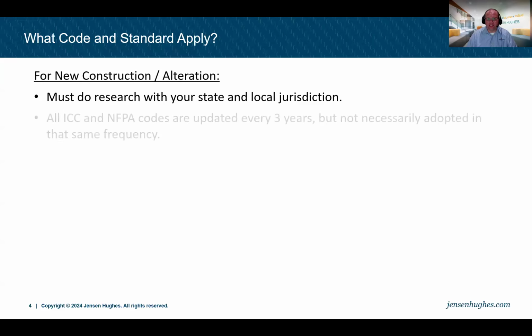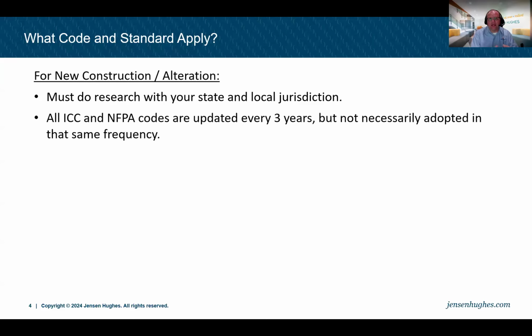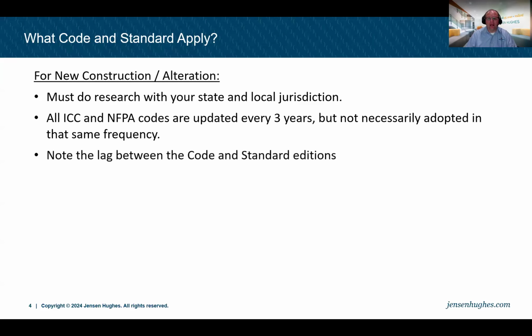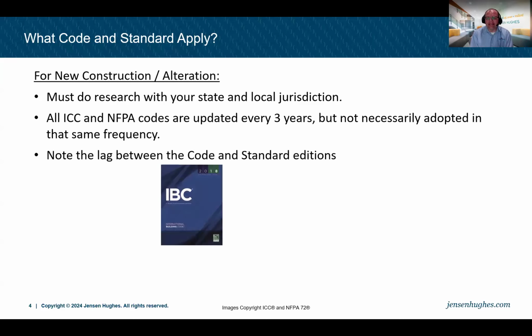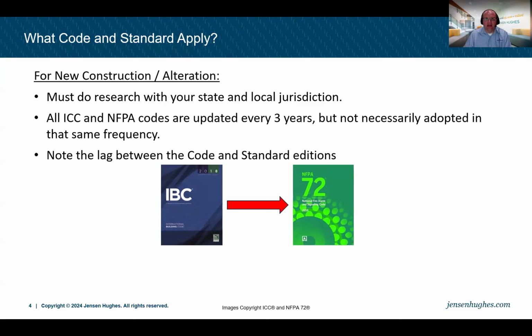Now, for new construction and alteration, the International Code Council and NFPA codes are updated every 3 years, but they're not necessarily adopted with that same frequency in your local jurisdiction. There's always going to be a lag between the code and the standard as it applies. Let's give you an example of that. If you were on the 2018 edition of the International Building Code, that code references the 2016 edition of NFPA 72. So that's the lag that we have, with the model building code being in the lead by, let's say, 2 or sometimes 3 years over the installation standard that it references.